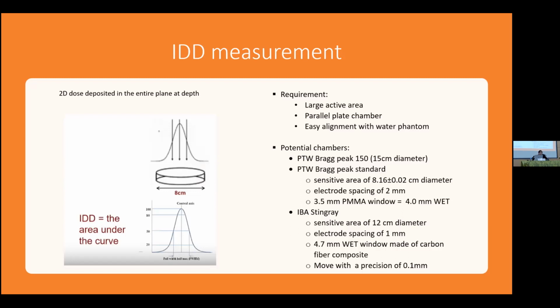There's different chambers that you can use. These are manufacturers, PTW. They make a Bragg Peak chamber. They call it the Bragg Peak 150. It has a 15 centimeter diameter. The PTW Bragg Peak, their standard one, has a sensitive volume about 8 cm diameter.